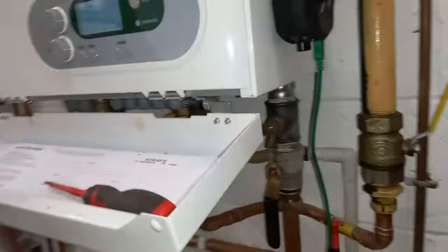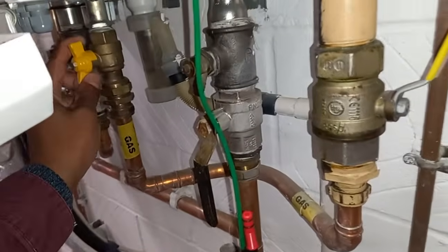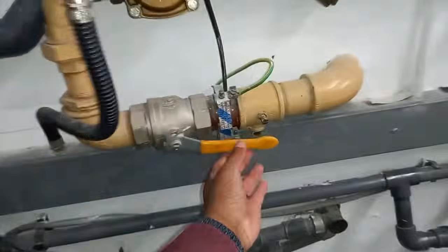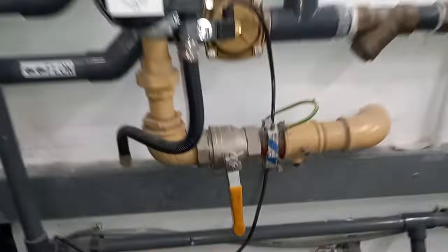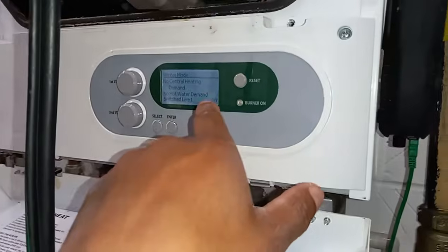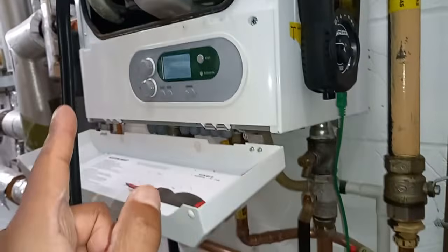I'm going to turn off my gas supply. I can turn it off here, or here, or I could go all the way over here and turn it off. So what I'm going to do is turn it off here, and do a local tightness test. The boiler's got no demand and it's not coming on, so that's good for me.